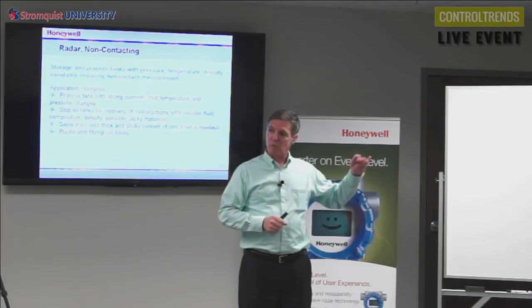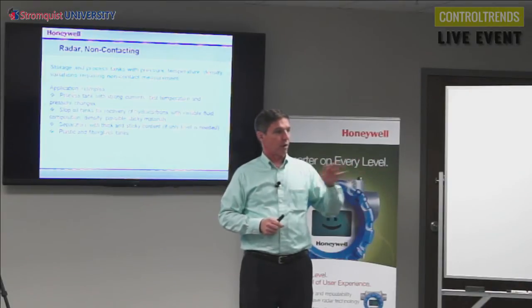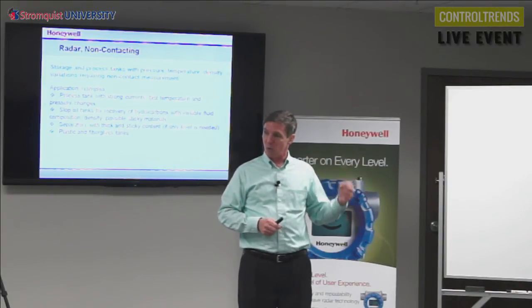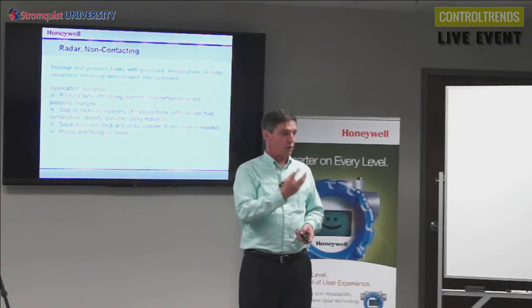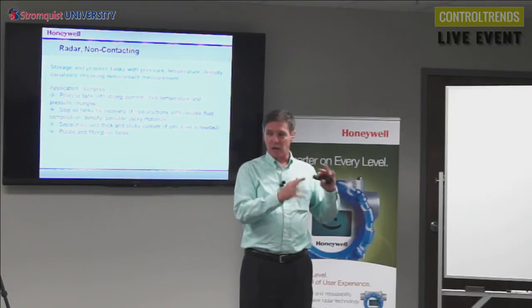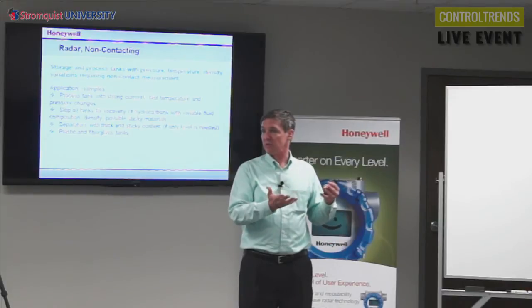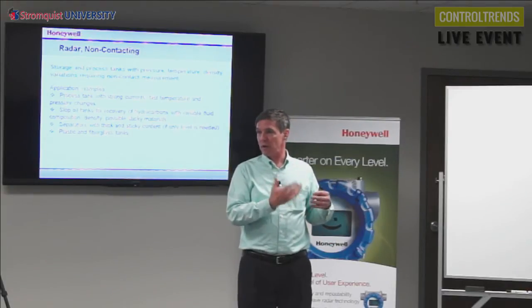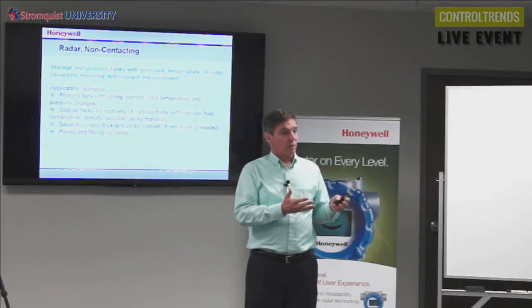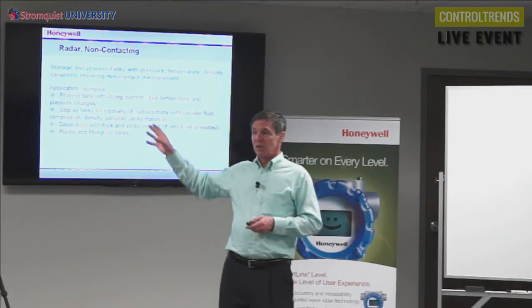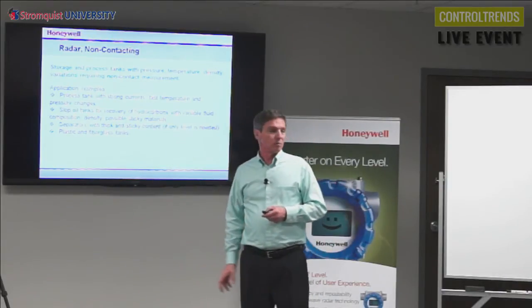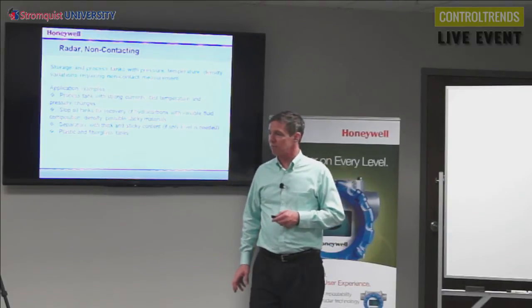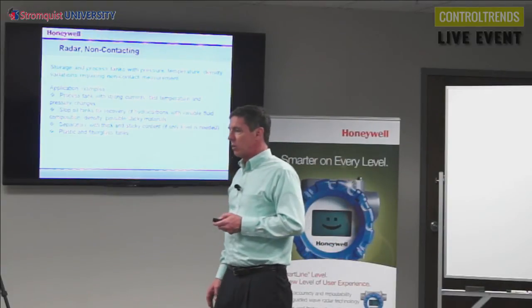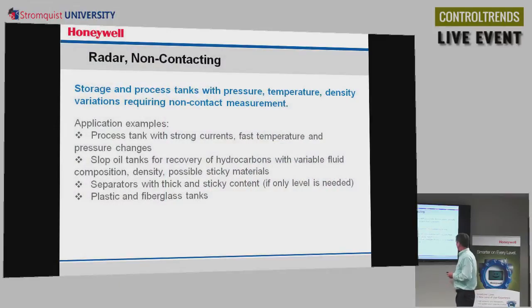Well, they don't just pump A and then stop and clean out the pipeline and pump B. They put one right behind the other, and there's sort of this rag layer between the two. It's kind of a mixture of product A and B, and that goes into the slop oil tank. It's not really something they can sell, and they don't really know what the density is. So radar is a good way to measure a product with an undetermined density. Could be in separators, and these work well in these plastic fiberglass tanks, the non-conductive ones that we had mentioned.